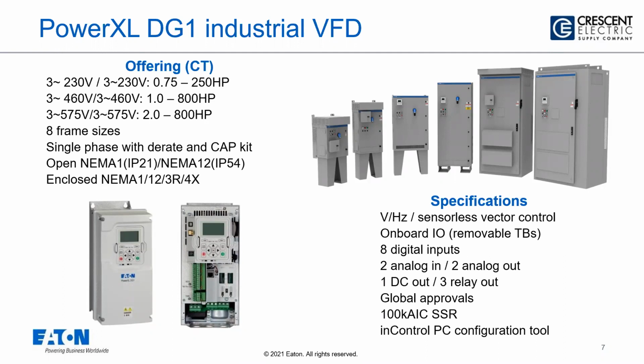We do have this standalone in a NEMA Type 1 or a NEMA Type 12 offering, and then it can be enclosed in a 12, 3R, 4X as well. So a lot of different packages for that. And from a standpoint of what this drive can do, it's your typical volts per hertz, but it can also do sensorless vector. So if you need to have tighter speed control, it has a lot of onboard I/O. So it has 8 digital inputs, 2 analog in, 2 analog out, and 3 relays. And those relays are 240 volt rated 5 amp relays. So they're very heavy duty relays.